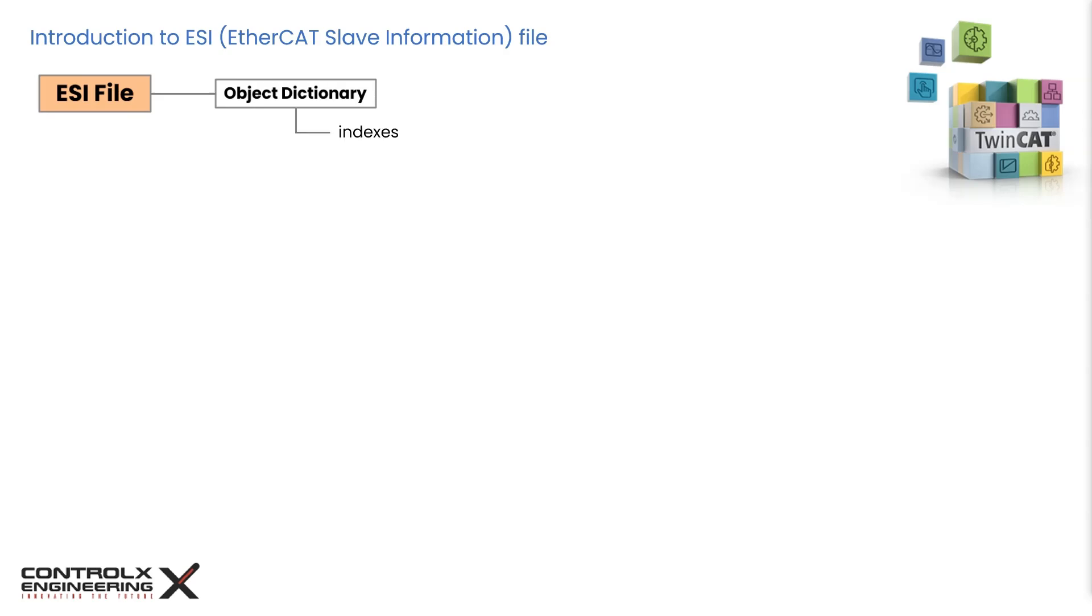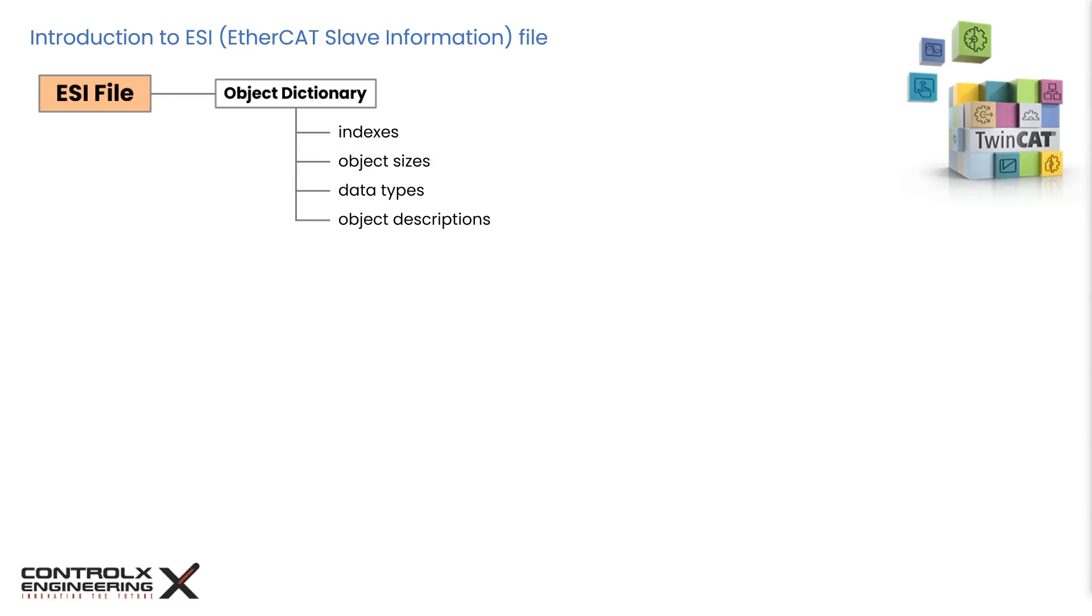It contains information about the device's object dictionary, which helps the EtherCAT master format commands and display the data correctly, since it contains the indexes, sizes, data types, and descriptions for each object defined in the file. ESI files are crucial for configuring and identifying EtherCAT devices within the network, ensuring proper communication and data exchange between the controller and the slave devices.